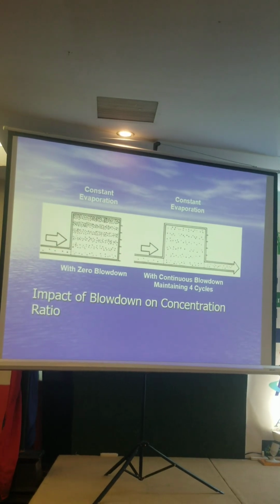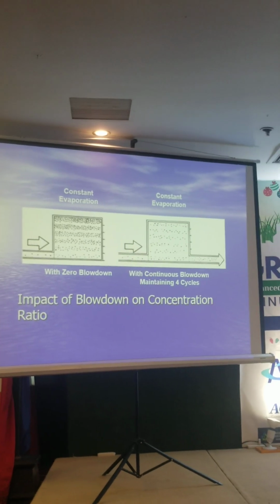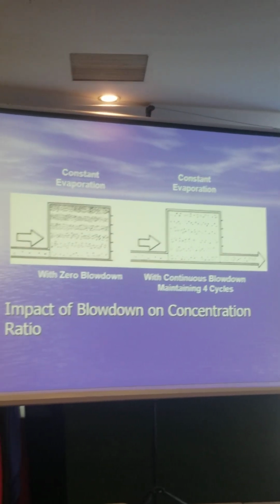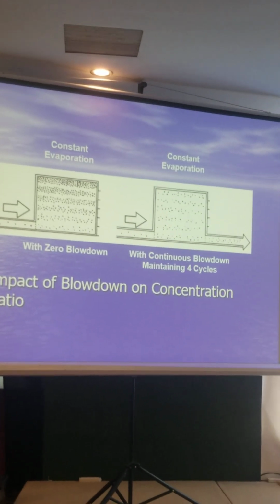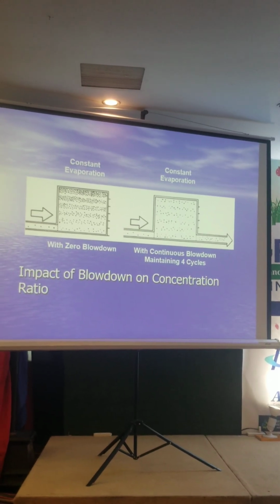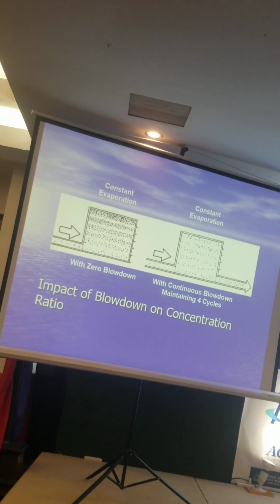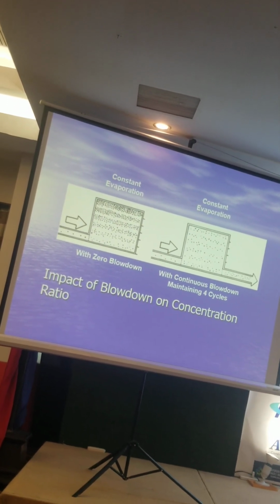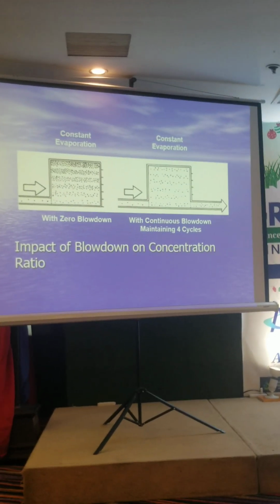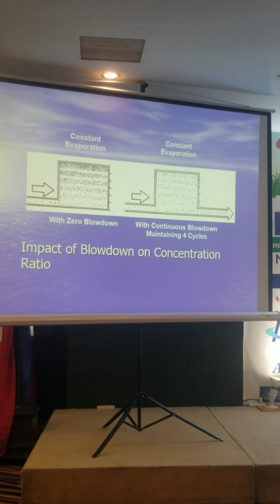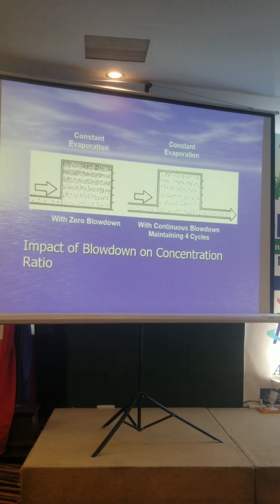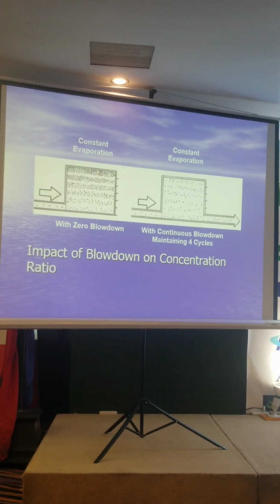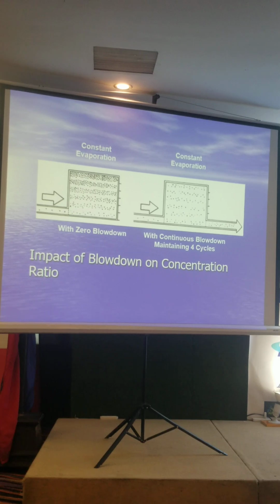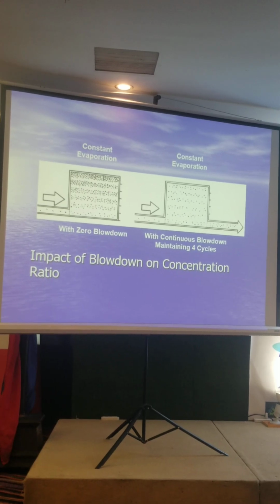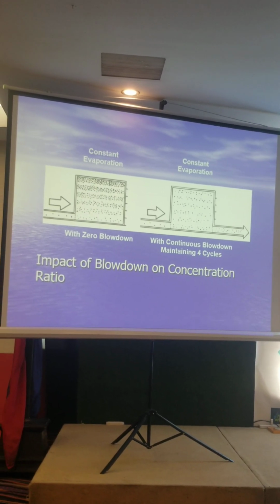When there is no blow down, minerals or dissolved solids concentrate in the system. You can see in the first picture, with zero blow down, there are a lot of solids. With blow down, the solids decrease. But blow down also affects the chemical treatment—the chemical is reduced when blow down is frequent.